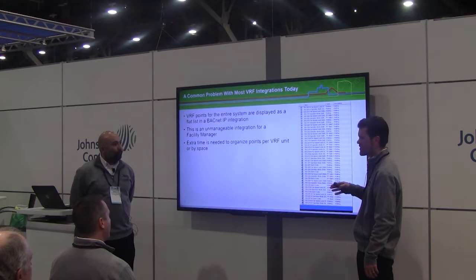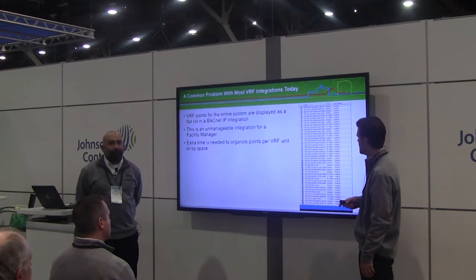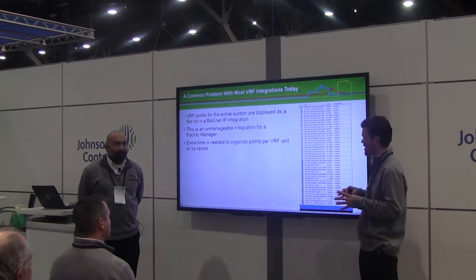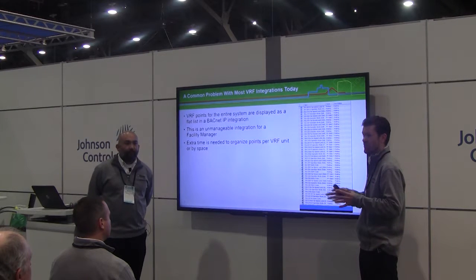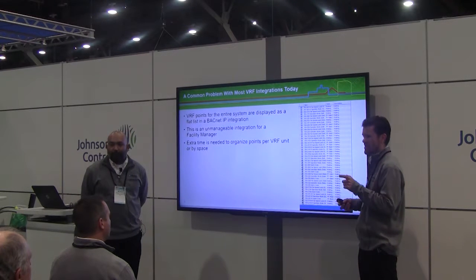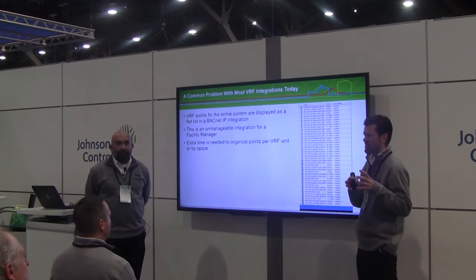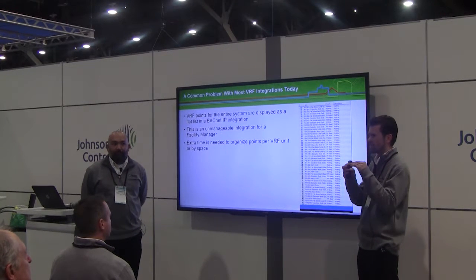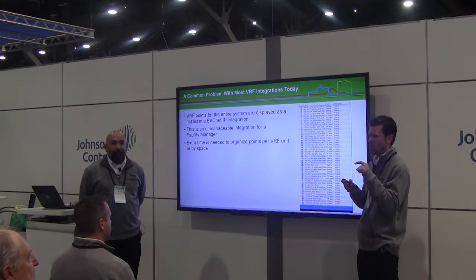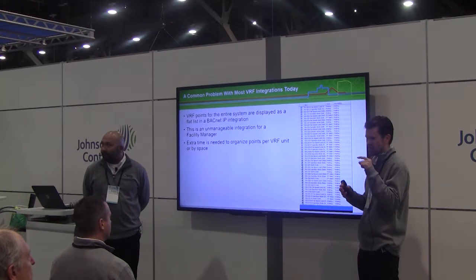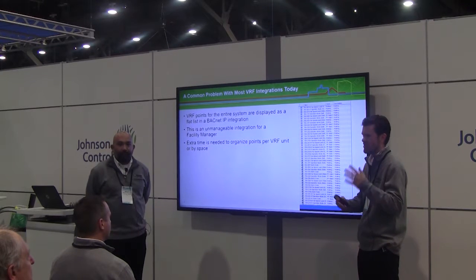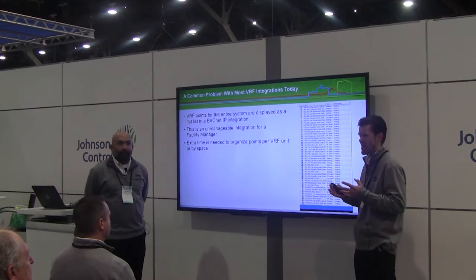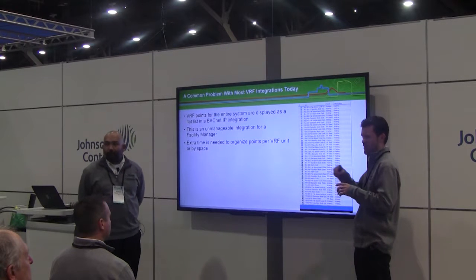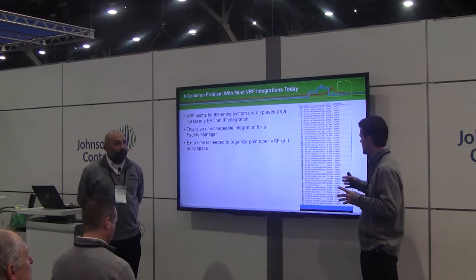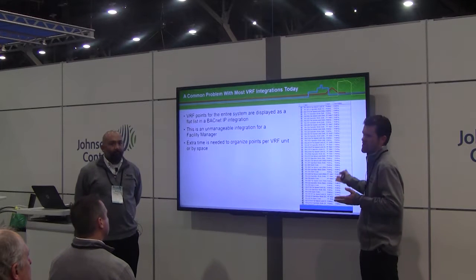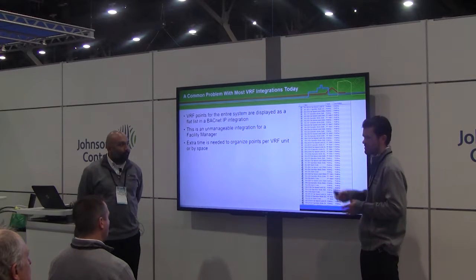A common problem with VRF integrations today is that when I go out through my building automation system to discover devices on the VRF system, I just get a gateway. That doesn't make much sense to me, but that's what I discover. Then when I want to map in the points, I get a flat list of about 200 points, and now I have to figure out how to organize these and determine which points belong to which unit. This is common across all VRF manufacturers today through their BACnet gateway.